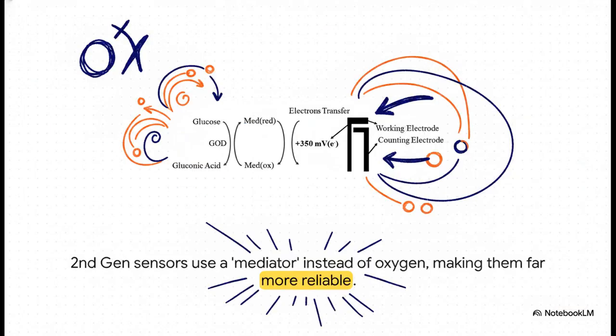So, for the second generation, engineers came up with this brilliant fix. They took oxygen completely out of the equation and replaced it with a chemical middleman called a mediator. This mediator's only job is to shuttle electrons directly from the enzyme to the electrode. This one little change made the sensor's reading totally independent of the oxygen in the blood. The result? Much more reliable and accurate measurements.